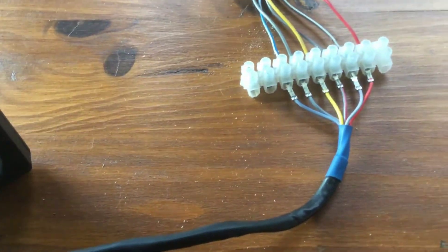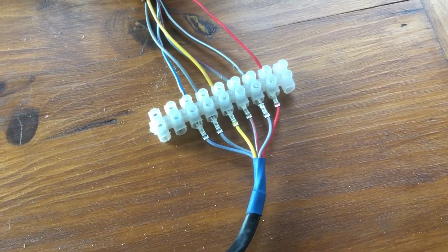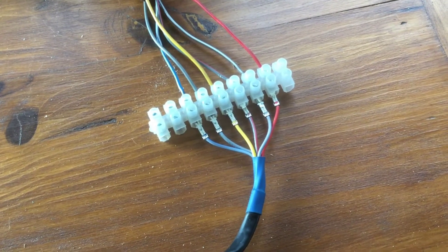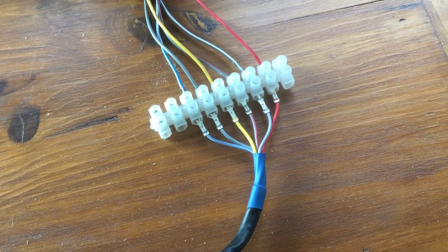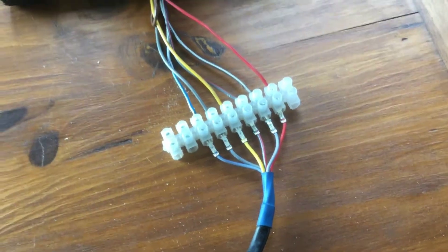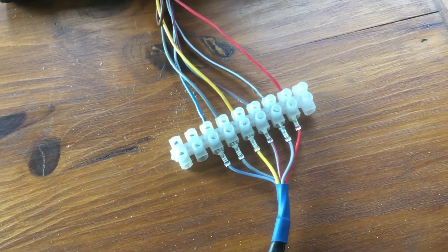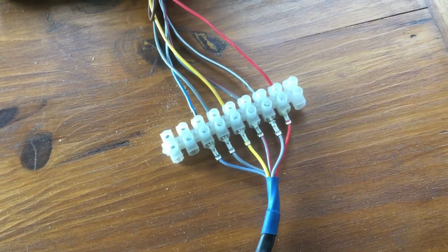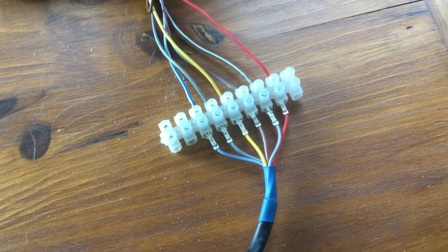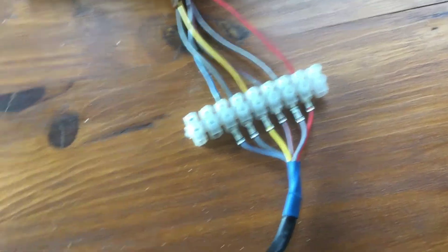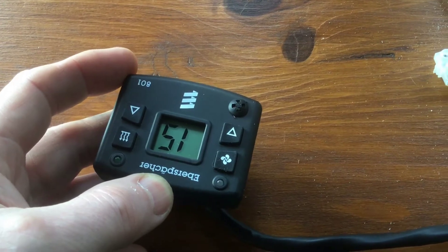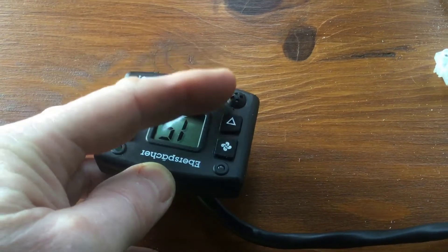So from left to right we have the blue and white wire. That is the diagnostic wire. Then we have a grey wire. That is the secondary temperature sensor that's on the front of the controller. There's actually two temperature sensors in an 801, that little thing there.